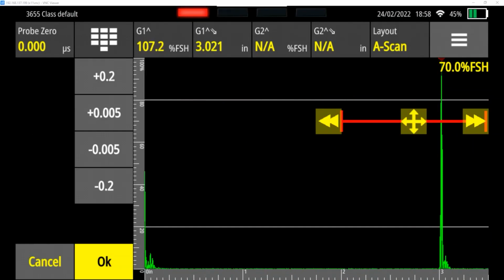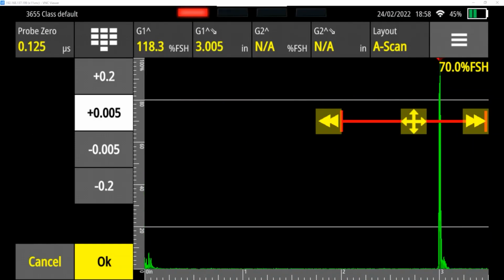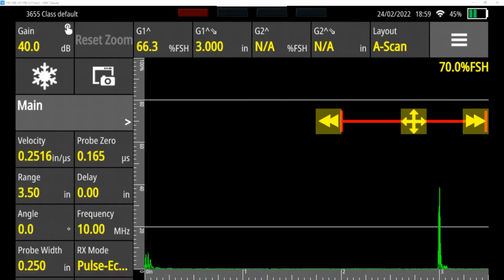So now I'm going to hit probe 0. And I'm going to start increasing that until my gate tells me that that echo is right at 3 inches exactly, because our block is 3 inches exactly. So it takes 0.165 microseconds for that pulse to get from the transducer, the piezoelectric transducer inside my probe, to the surface of the piece I'm testing. So now our transducer and our velocity are matched to the material we have.